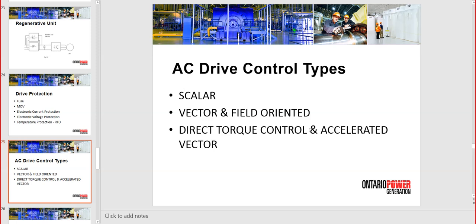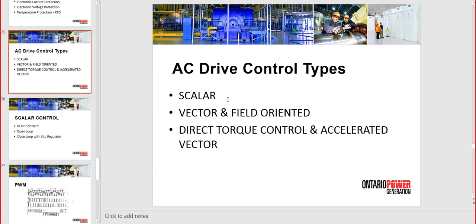Direct torque control is a variant developed by ABB, developed in 1986 for torque applications. It is a simplified vector control, knowing where the acceleration needs to go, it is tabulated in the memory, and less calculation is required. So now when you order a drive, you can order a scalar drive as control goes, or you can order a vector. When you order a vector drive, the difference in price will be minimal, a couple of $100, because it's only intelligence in the drive that is extra. But you have the possibility to switch to vector if required, so if your application doesn't handle the load properly with a scalar algorithm, you can switch to the vector algorithm and solve the problem.